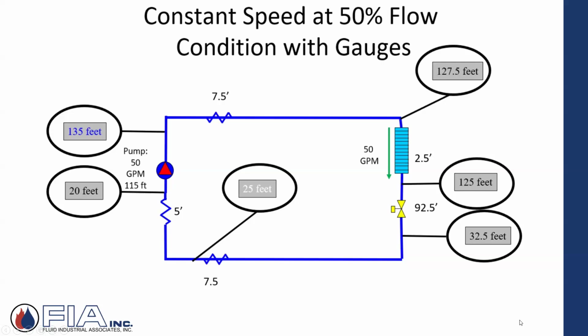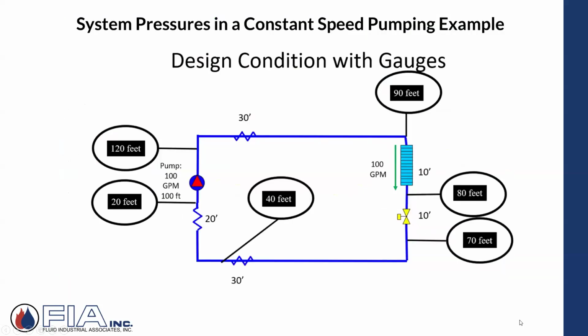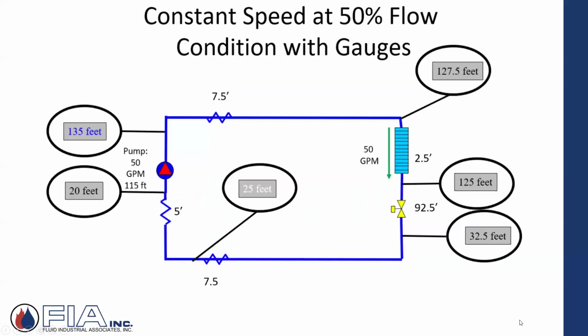But you still have this constant speed. We haven't introduced variable yet. And this is the reason why we went to variable, why the industry was desperately trying to get there a while back. Now all of a sudden that control valve that had 10 feet of head loss is now responsible for absorbing 90 feet, 92.5 feet of head loss. That's excessive. That's real velocity or maybe erosion. It's necessary, it's what we need to do, but that's the limitation, as well as waste perhaps of some energy with constant speed.